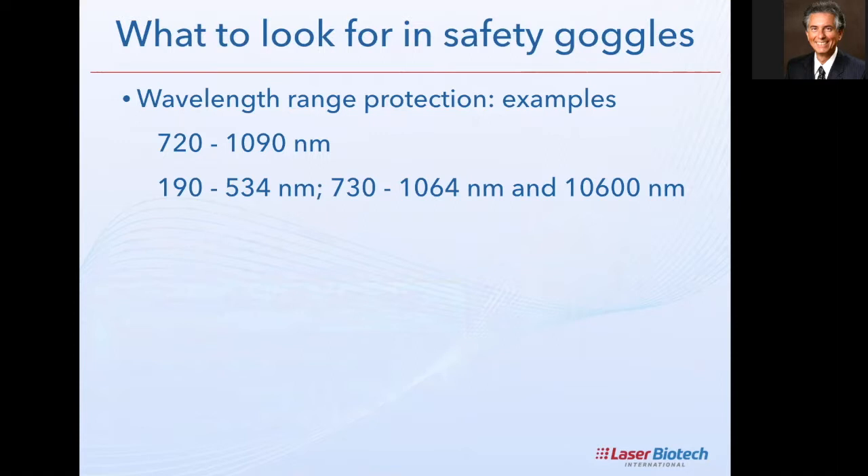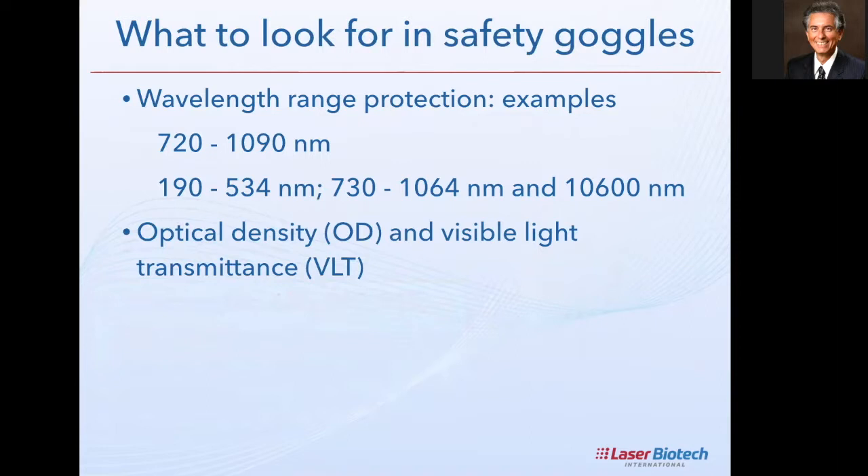This second example goes up to 1064 nm and also covers 10,600 nm — the CO2 gas laser. The range 730 to 1064 covers all Lumenis laser wavelengths except 650 nm. There are two key numbers to look at: OD (optical density) — the level of infrared protection — and VLT (visible light transmittance) — how light or dark the lenses are. A higher OD number means higher protection; for example, an OD of 7 is very high protection for infrared emissions.